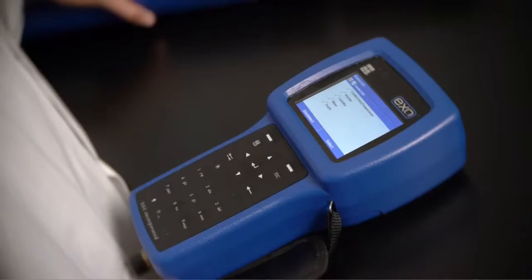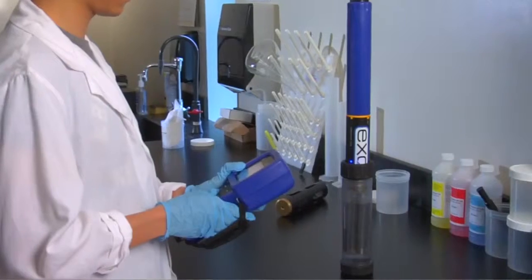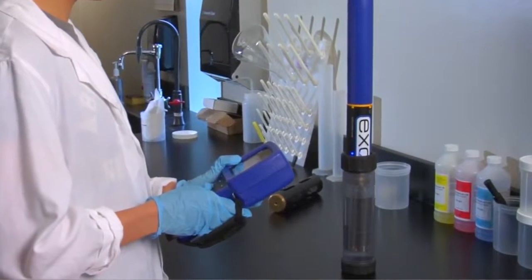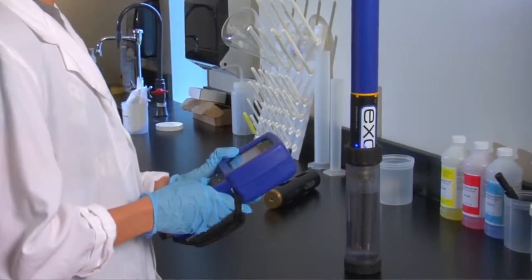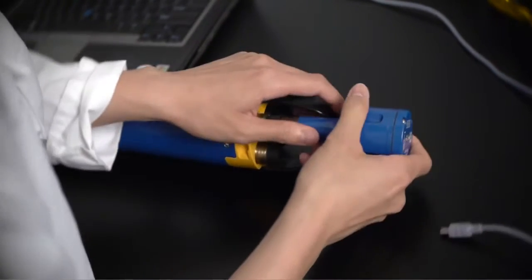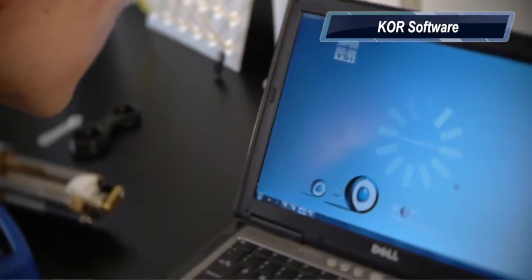So let's look at the laboratory for calibration, for example. You can load up a sonde with 6 turbidity sensors around a centralized wiper, and you can calibrate all of those at one time. That saves you a lot of time and it saves you a lot of calibration standard. You're using about 16% of the calibration standard you would use if you calibrated each one of those independently with good laboratory practices. It has a very intuitive interface. It's very user-friendly, not just the equipment itself, but the KOR software as well.